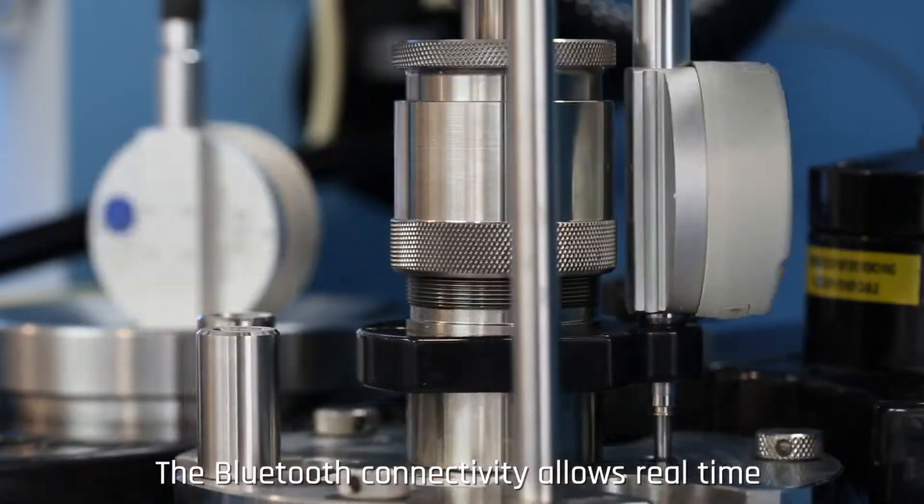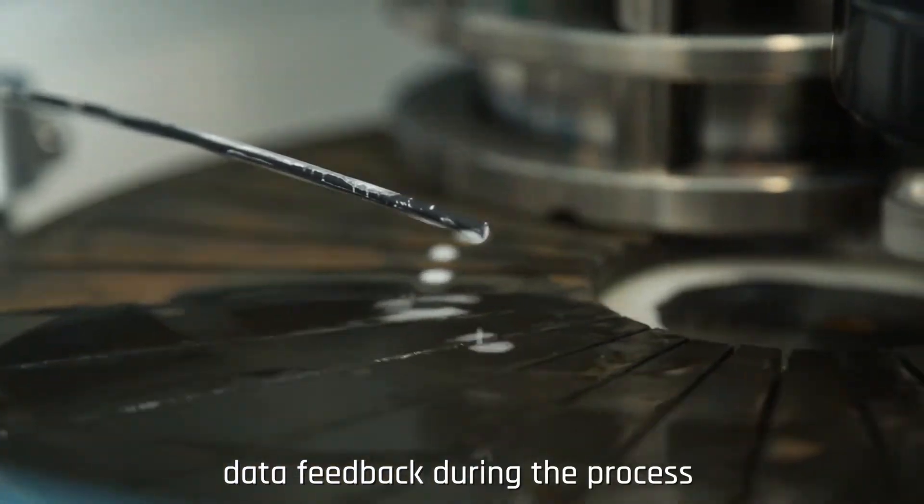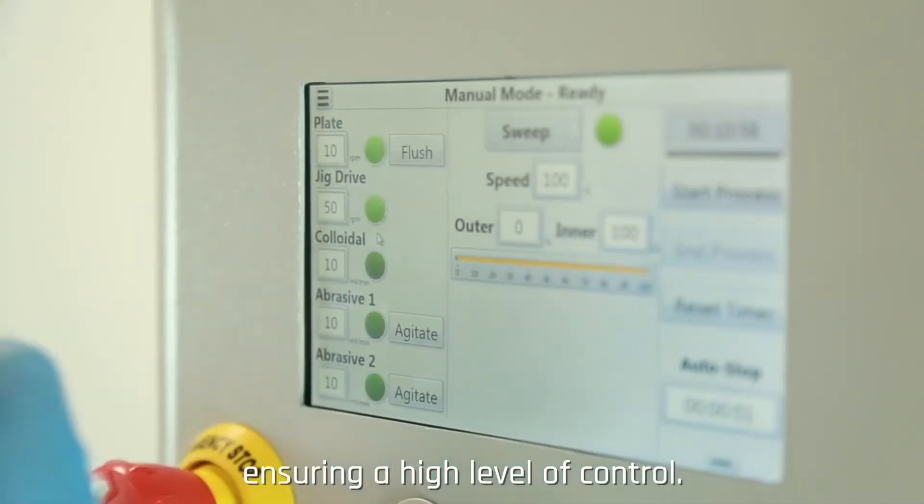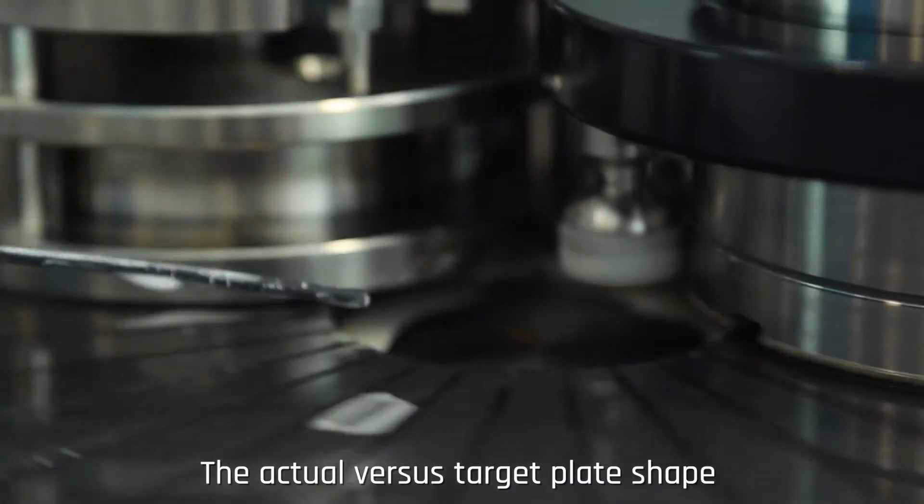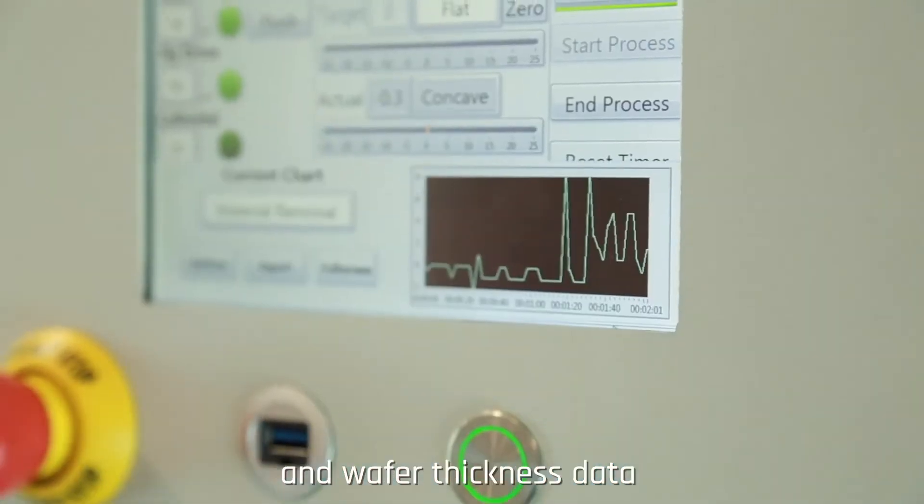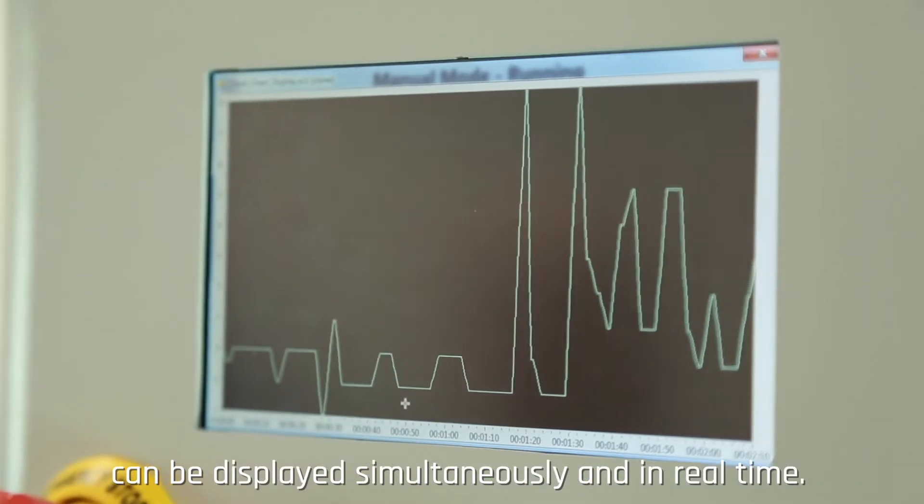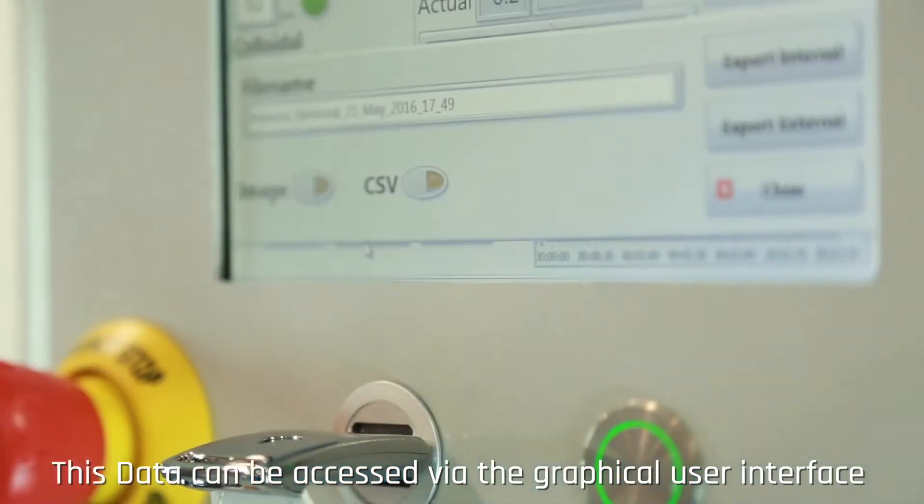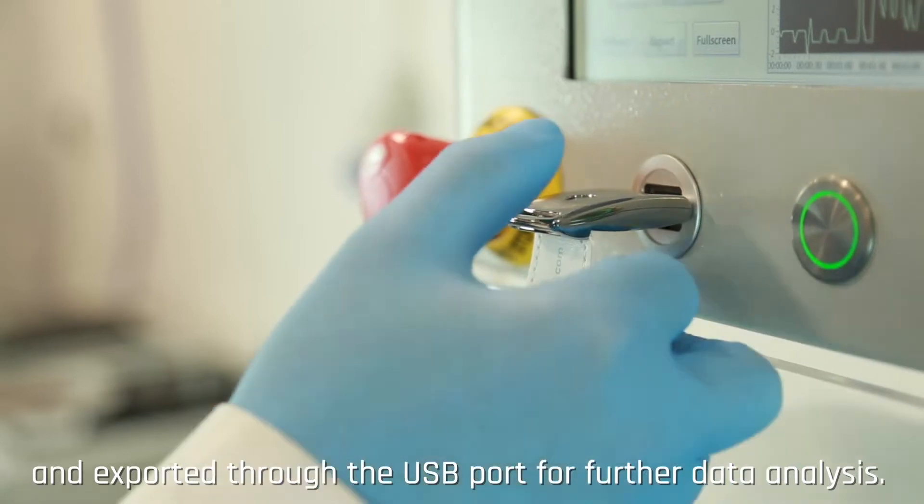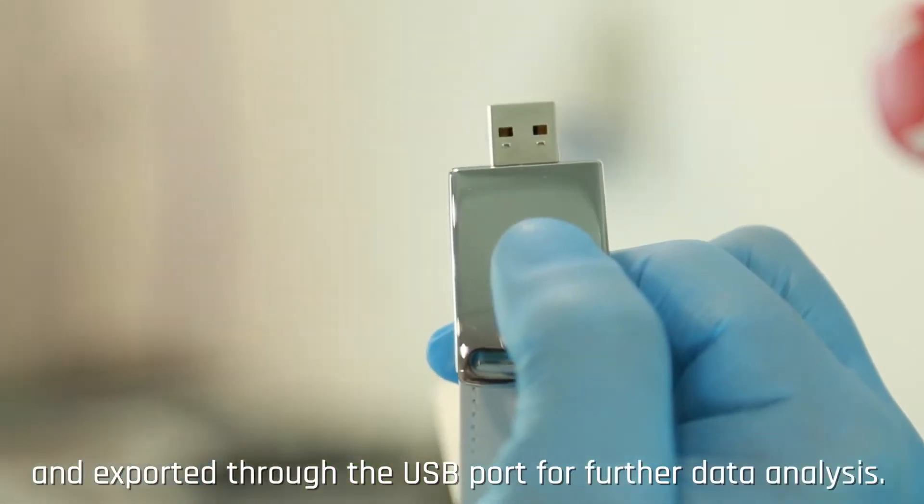The Bluetooth connectivity allows real-time data feedback during the process ensuring a high level of control. The actual versus target plate shape and wafer thickness data can be displayed simultaneously and in real-time. This data can be accessed via the graphical user interface and exported through the USB port for further data analysis.